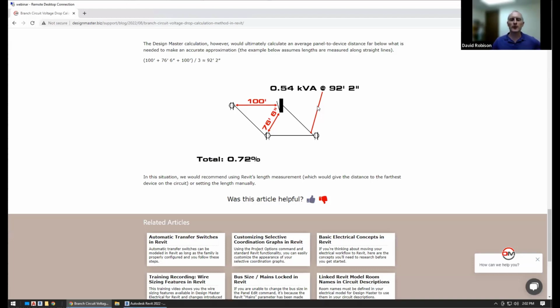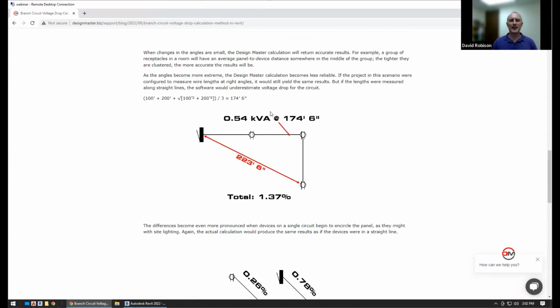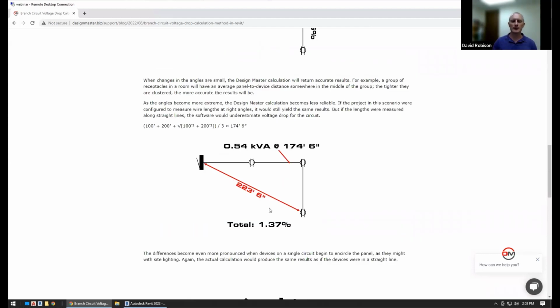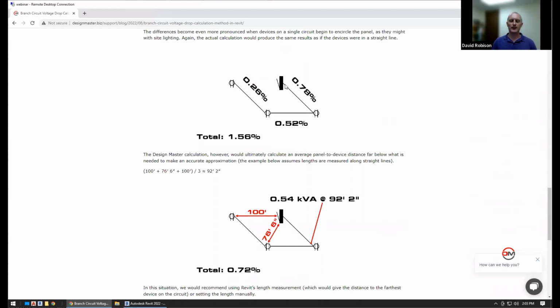So that is what we're doing with our calculations of our lengths and how that then impacts the voltage drop. As long as you're in this case here, where you've got them all in the same direction away from the panel, it ends up working out. If they are longer runs, it might end up mattering a little bit. And if you have cases where they're circling around, that's where it's going to be less precise. And you might need to calculate those separately if you're concerned about the voltage drop on a circuit like that.